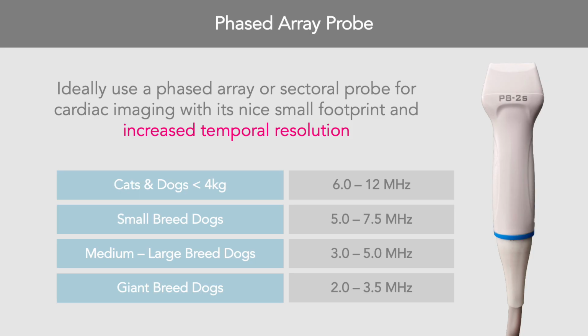The phased array probe, like many other transducers, is very often a multi-frequency probe. However, the range of frequencies attainable is much smaller than the microconvex probe. Therefore, it can often be necessary to have a probe suitable for cats, middle-sized dogs, and a third for giant breeds. That's life goals right there. Most clinics do generally only have one. It's typically the size for sort of medium-sized dogs.